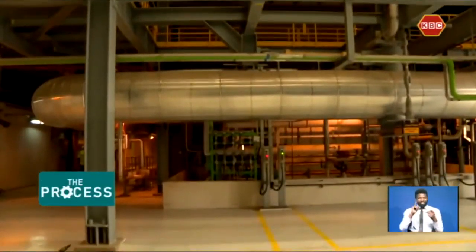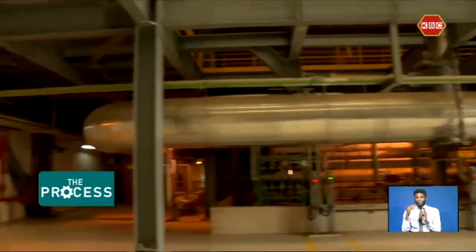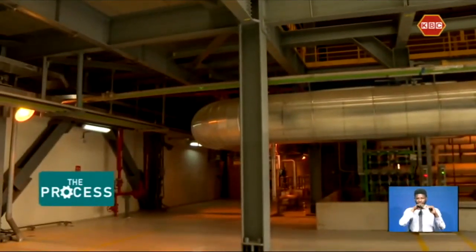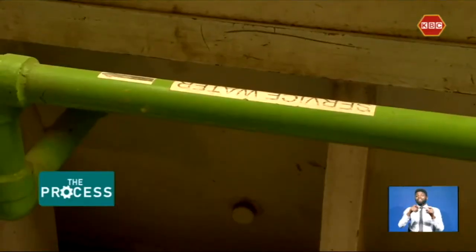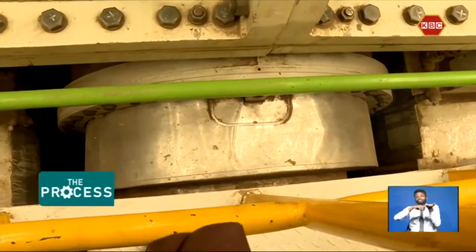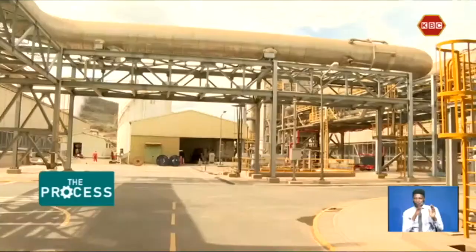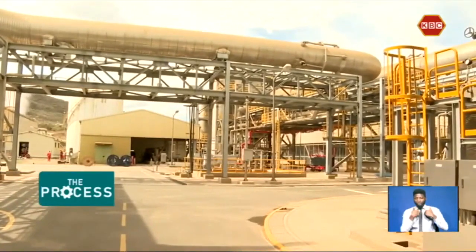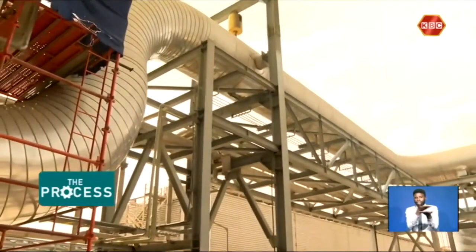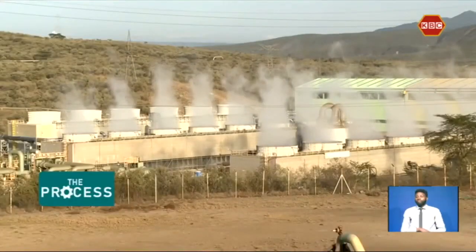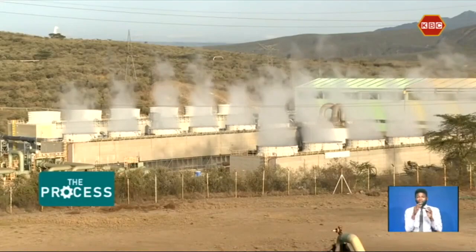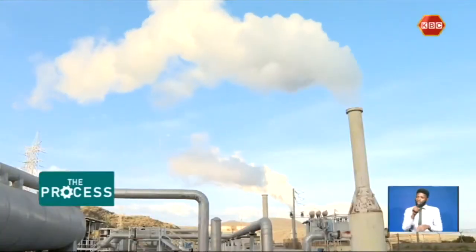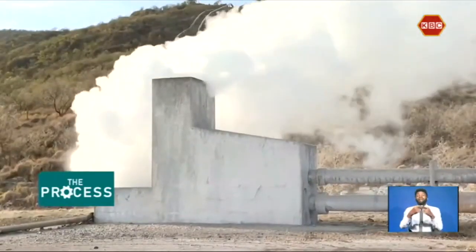The steam enters the power plant and goes through a separator that separates the water and the steam and ensures that no water gets into the turbine. Once the steam is at the plant, we take it through a steam scrubber, and the objective is to remove any water that has remained or that has come with the steam. The steam must be 99.99% dry to be able to operate the turbine in a safe way.